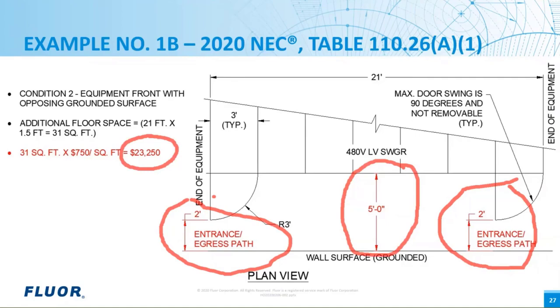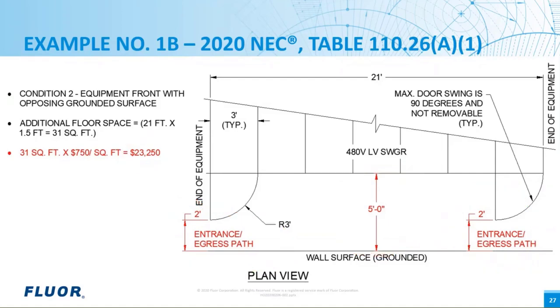Now we know this entrance and egress path is something reasonable, and it's good to keep workers from being trapped in a workspace if something occurs. Something we will need to think about though, what's going to happen in existing facilities when equipment is old or damaged and it needs to be replaced? This is really going to have to be worked on a case-by-case basis. But as I said, there's no exceptions in the 2020 NEC to allow new equipment to be installed in existing facilities and not comply with the minimum 24-inch entrance and egress out of the working space.